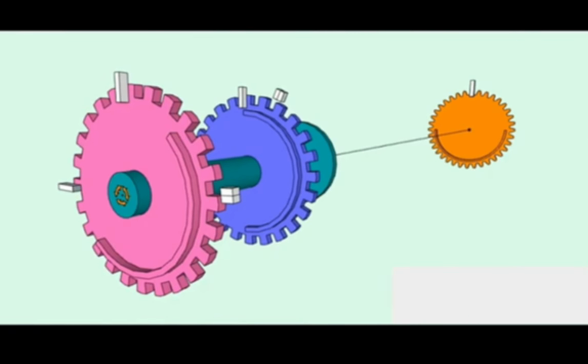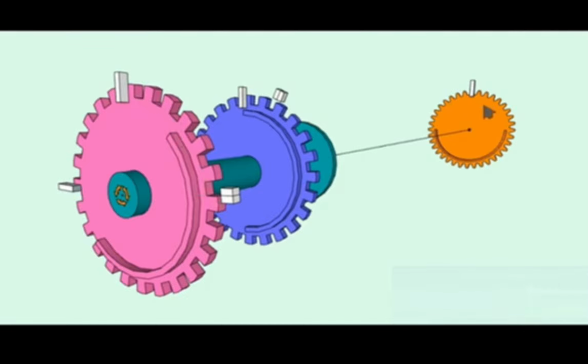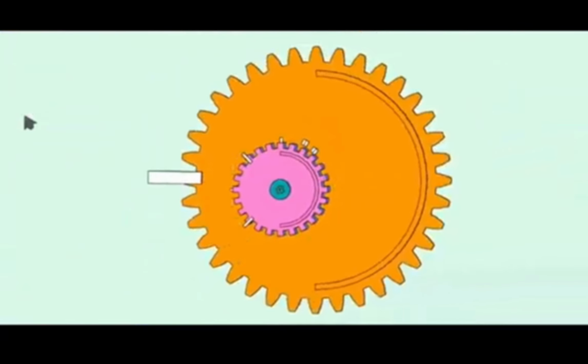Now you can see that we have this many sensors. The main, big sensors are the marker sensors, 2 marker sensors in one encoder, which are 90-degree offset, and the small sensors fitted together are called quadrature sensors. These are for calculating the RPM as well as the direction of the shaft. And this is the setup.